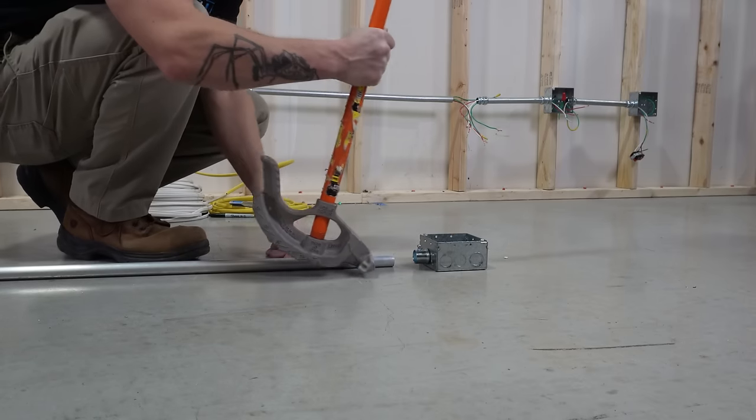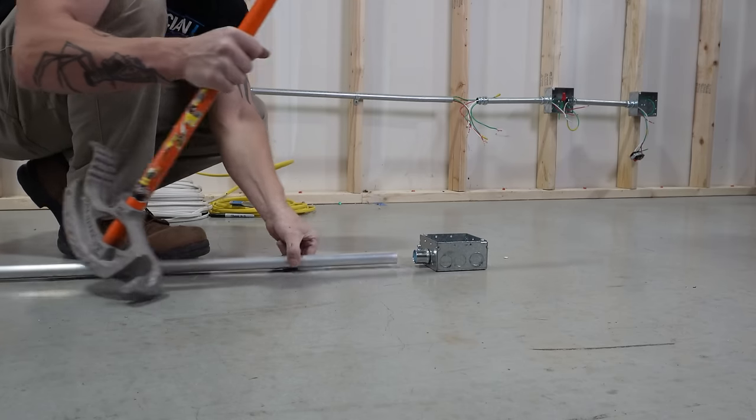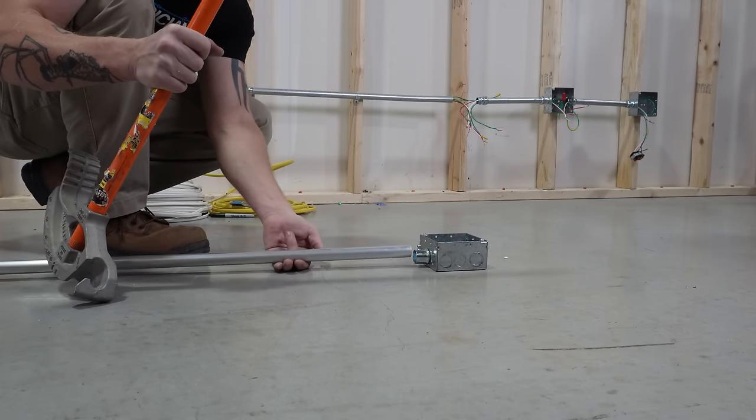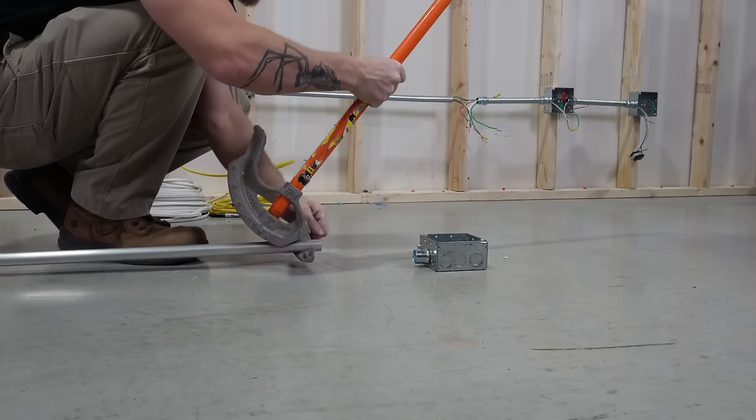Now you could come back and start way back here, but then you're going to have all of this that's above here and it's not going to come back to the ground until back here. So usually I do all my box offsets starting at the very end of the bender.